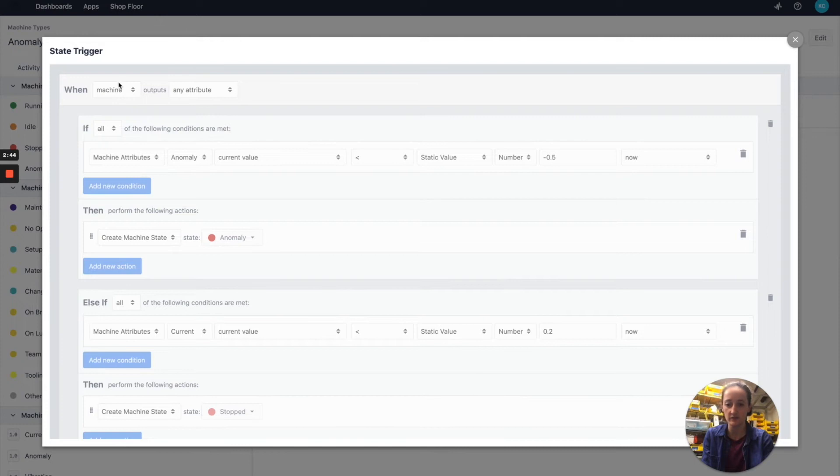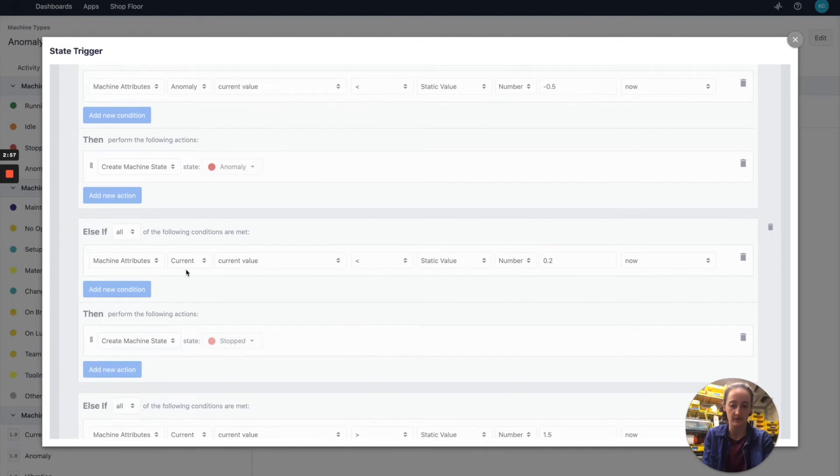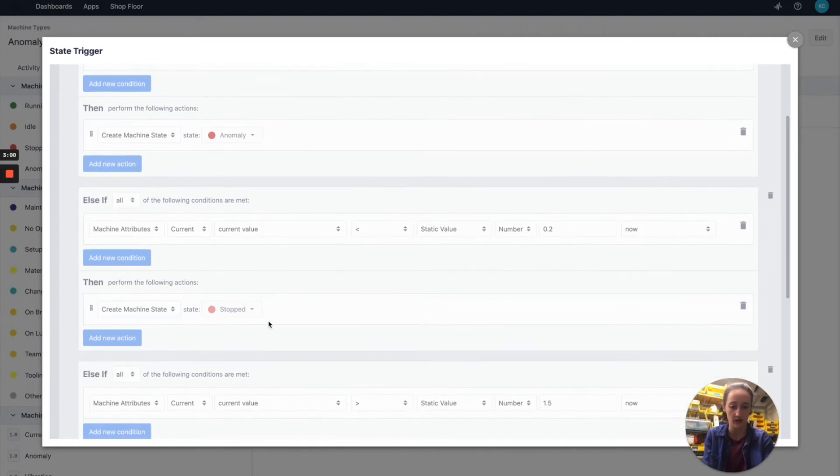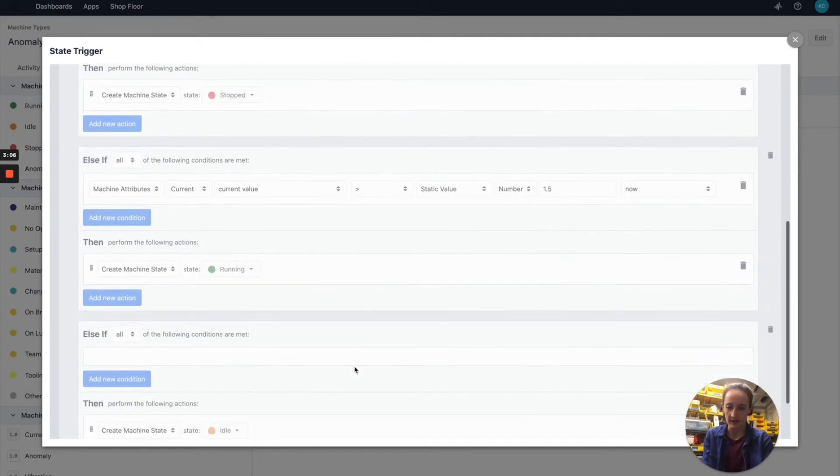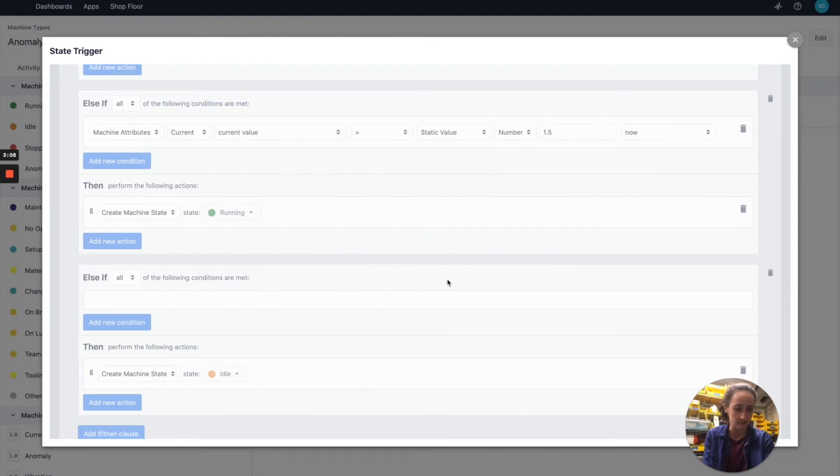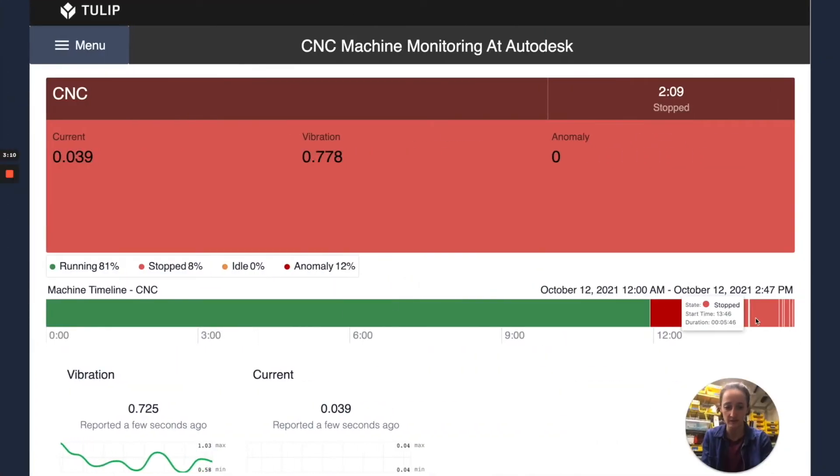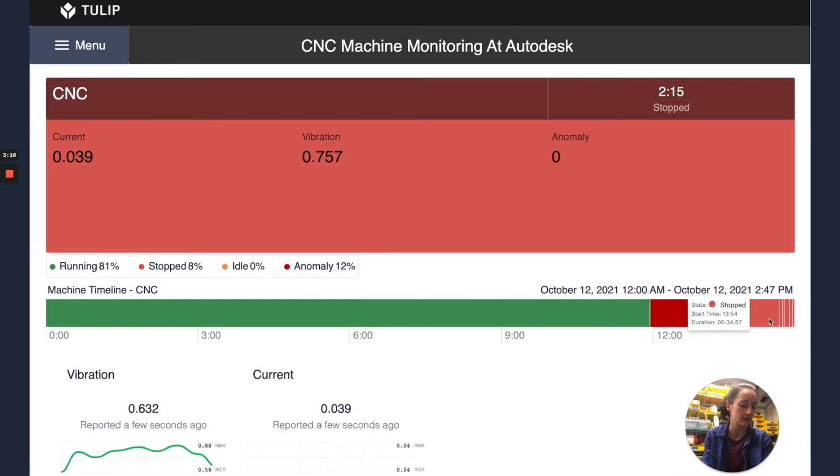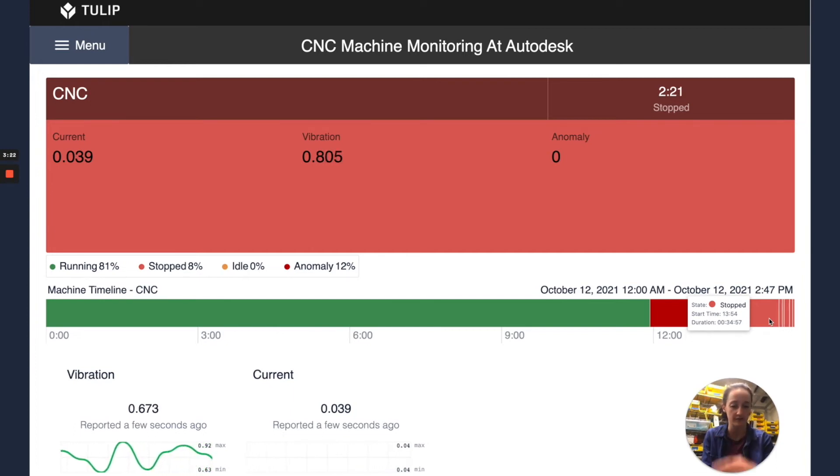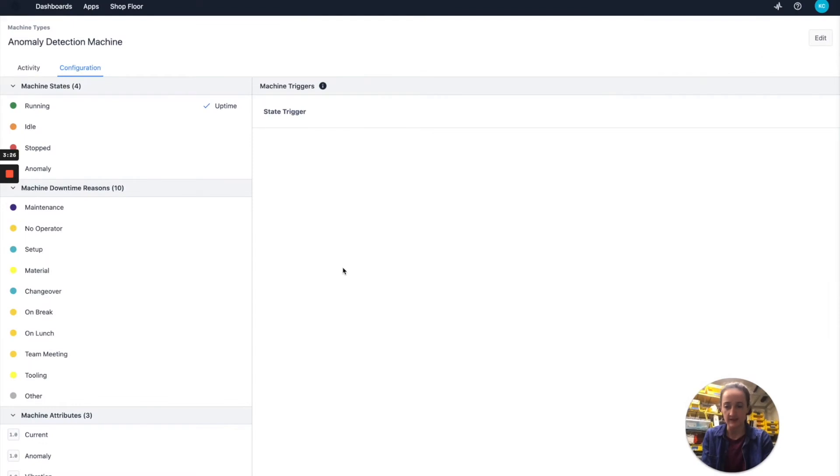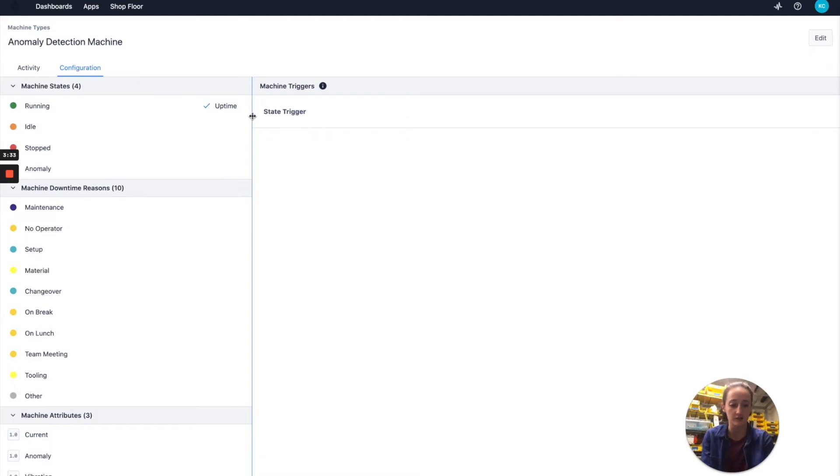In this state trigger we can see that whenever the machine outputs an anomaly we set the machine state to anomaly, and whenever we output various current values we set the machine state to other things. For example, a current of less than 0.2 amps being stopped, a current value of greater than 1.5 amps will set the state to running, and anything else will set the state to idle. So here in this machine timeline widget these states of running, anomaly, and stopped were based on either there being an anomaly output or the current values reporting on or off for the machine. Now that we know how the state's getting set and how the attributes are displaying in the app, let's see where this data is actually coming from.